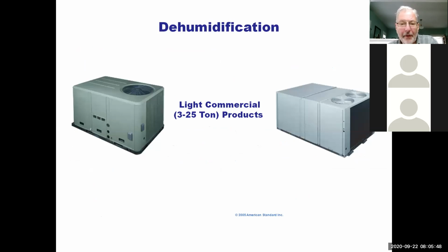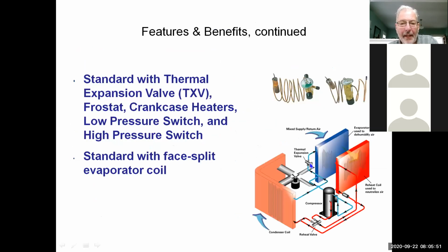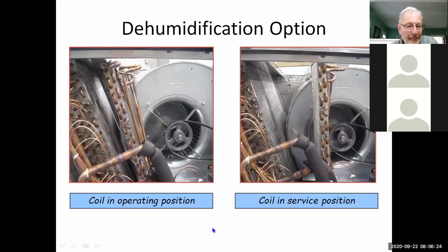All right, we also have dehumidification rooftops, and basically it has an evaporator coil and a condenser coil in front of the evaporator coil. And it has a switchover valve, a 3-way valve here. So when you go into dehumidification, it pumps through this condenser coil rather than this one. And this coil is still a little smaller than the evap coil, so it will net cool. I mean, it's going to start to cool, and they can actually overcool if you get into the right situation. So be aware of that. They pack a lot of stuff in there. And as you can see, the condenser coil is not as big as the evaporator coil, so it will still tend to overcool.